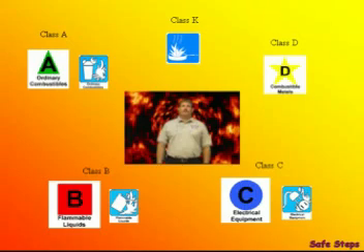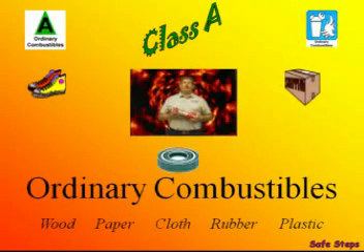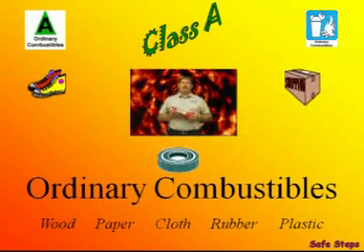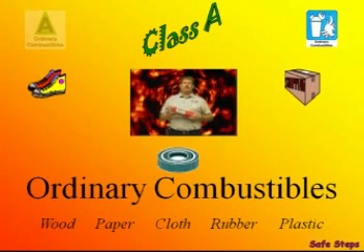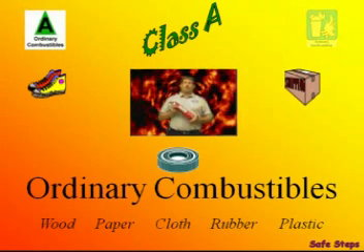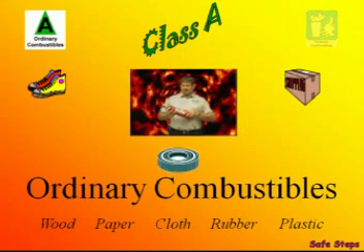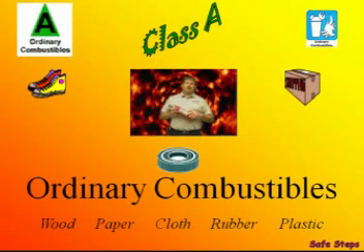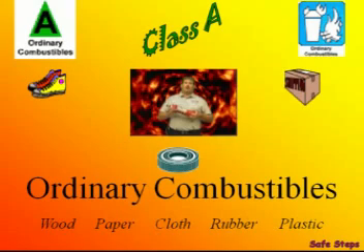Ordinary combustible materials such as wood, paper, and cloth make up the A class. Normally if it produces an ash, it's considered Class A. Class A fire extinguishers are symbolized by the letter A inside of a triangle. If the triangle is color-coded, it'll be green. The universal picture symbol for a Class A fire extinguisher is a trash can and wood burning. So when you look at the label, if you see the letter A inside the triangle or the trash can and wood burning, you'll know that extinguisher is good for a Class A fire.